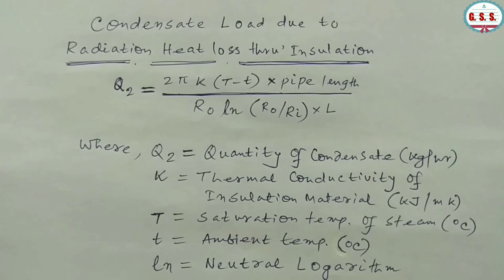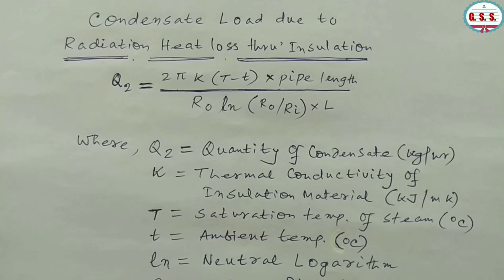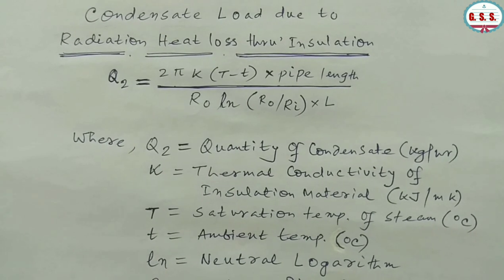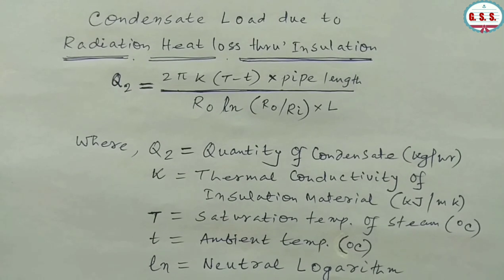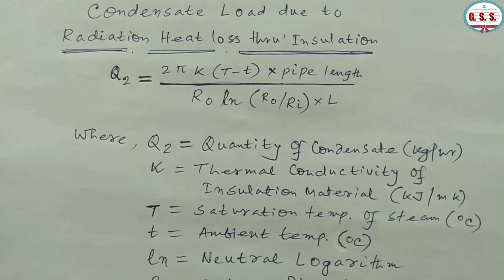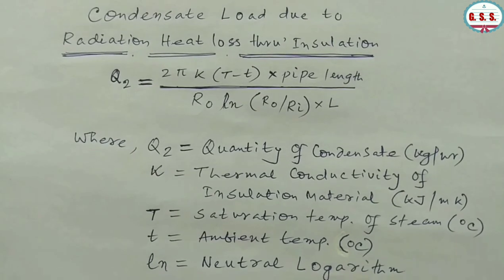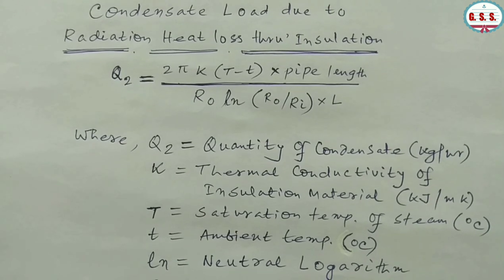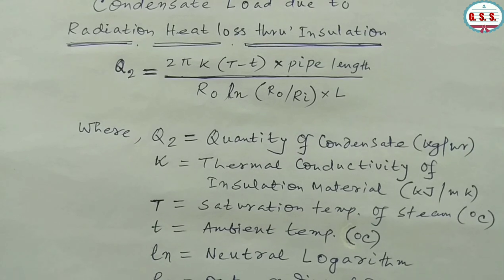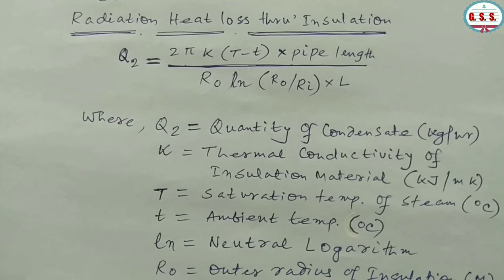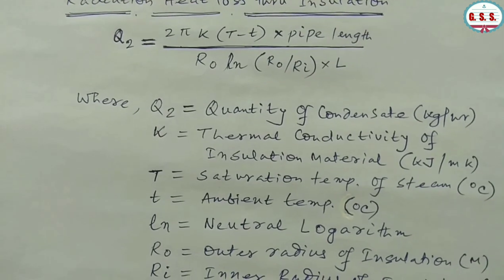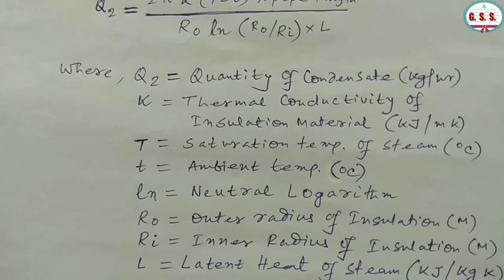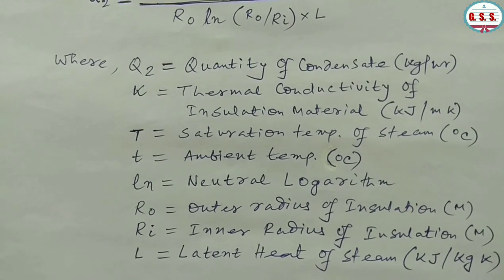Condensate load due to radiation heat loss through insulation under normal running condition: Q2 = (2π × K × (T − t) × pipe length) / (R0 × ln(R0/Ri) × L), where Q2 is quantity of condensate in kg/hr, K is thermal conductivity of insulation material in kJ/(m·K), T is saturation temperature of steam in °C, t is ambient temperature in °C, ln is natural logarithm, R0 is outer radius of insulation in meters, Ri is inner radius of insulation in meters, and L is latent heat of steam in kJ/kg.